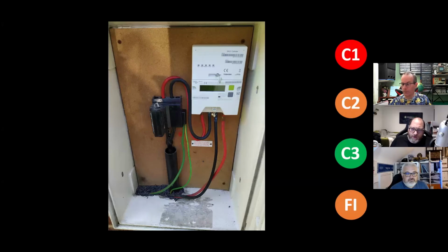Could be either. Limitations, because an FI would be unsatisfactory. Yeah, limitations generally, because in most cases, unless you're going to hook the seals off, you're not going to see the fuse rating. So most of these, certainly domestic ones, go down as a limitation for the fuse. Cool. Mainly because what else are you going to do?